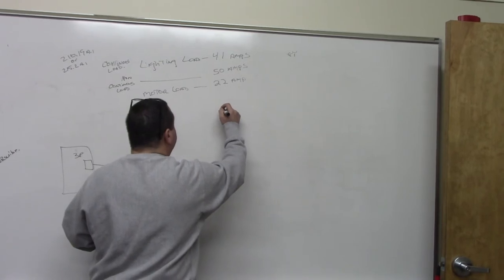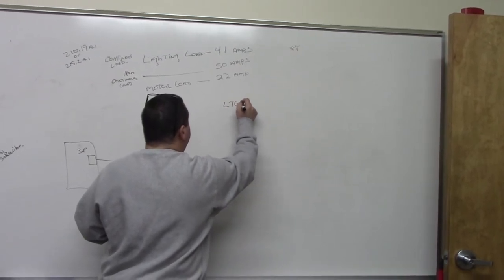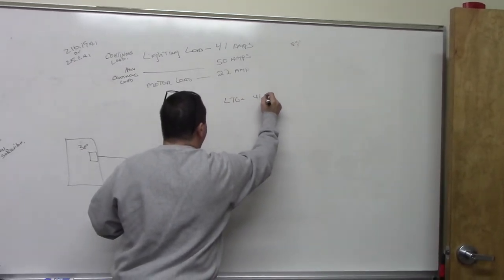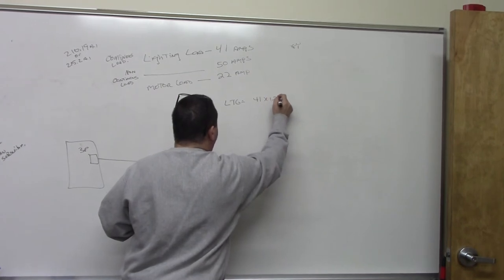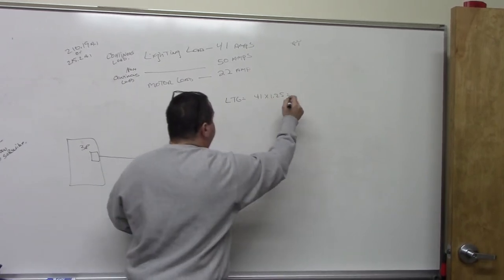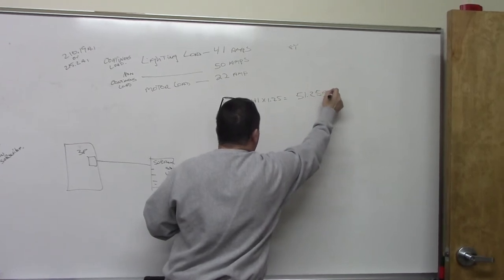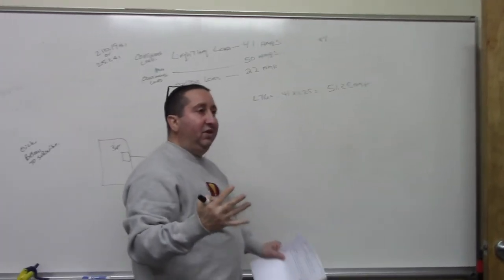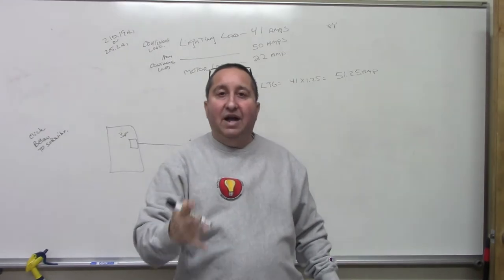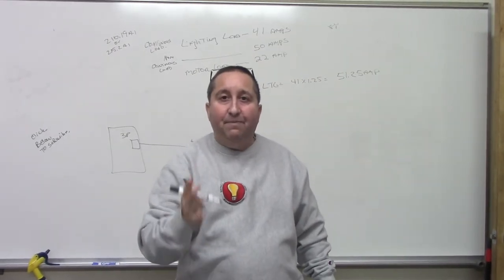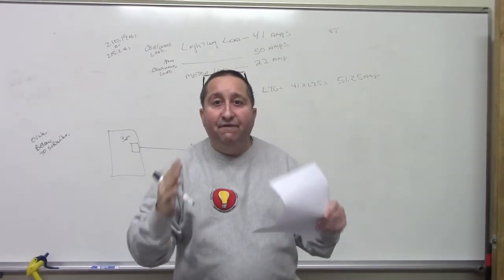So basically, your lighting load, lighting is equal to 41 amps times 1.25 continuous load, which is 51.25 amps. Remember, as soon as you do lighting, other than dwellings, you've got to add 125%. Very, very important.